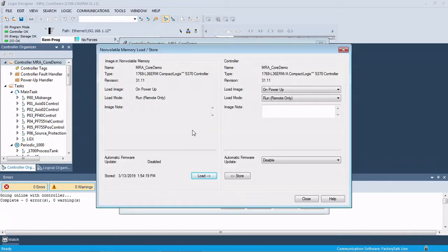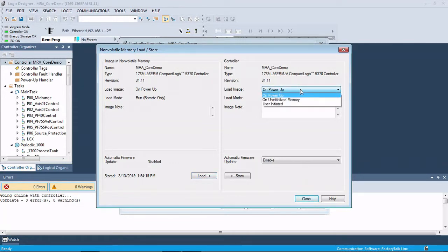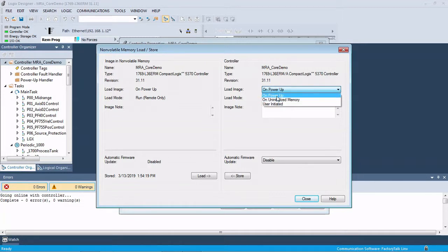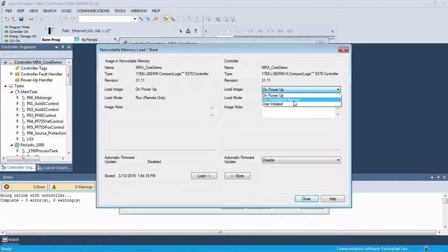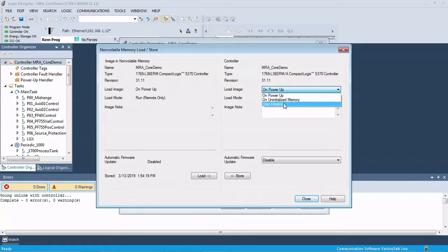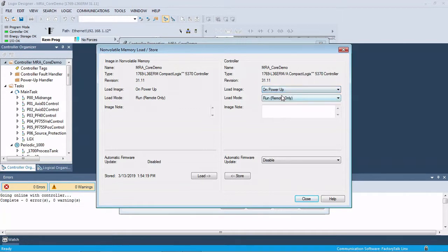So here you have some choices. When do you want to load this image? Power up would be anytime that the processor powers up, it goes ahead and loads the image off the SD card. Uninitialized memory would be some sort of corrupt memory if something went wrong in the processor. It would reload the firmware and the program to fix the controller. And user initiated would have to be manual. So somebody would have to come into Studio 5000, go online, and load from the card.